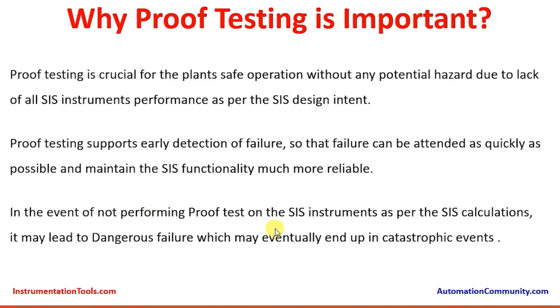In the event of not performing proof testing on SIS instruments as per the SIS calculations, it may lead to dangerous failures which may eventually end up in catastrophic events. For example, due to some reasons the plant is running, instruments cannot be isolated, and the proof test is missed. If there is a demand coming as a safety requirement and the instruments did not work — the pressure sensor which is supposed to sense the pressure and give an indication to the logic solver to give a closure to the final containment valve — and either its electronics or its sensing components like the diaphragm failed, this cannot be detected.